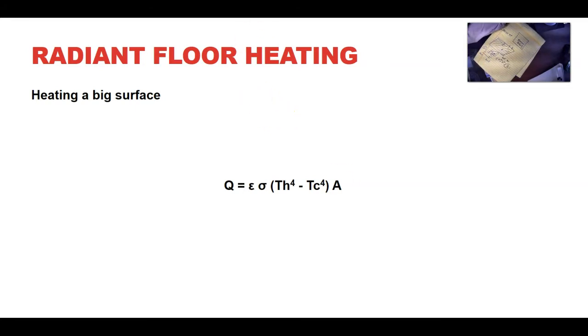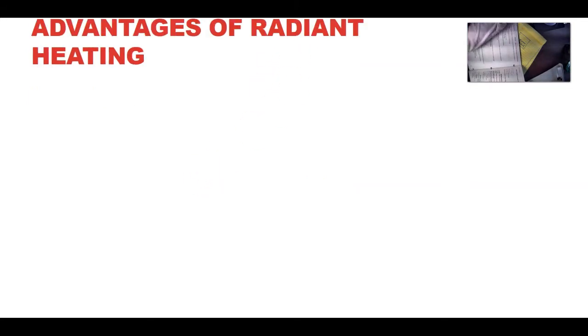Okay, enough of that. If you look at your book, on the last page is your equation, which gives you the radiation rate. If you want to calculate selection, go to radiator selection. This is for steam, this is for water, and this is the equation we just used last video. And here is our equation given for radiation. Q is the radiation rate, and area is the area available to radiate heat, whether it's floor or wall, and the temperature difference is between the water and the room.